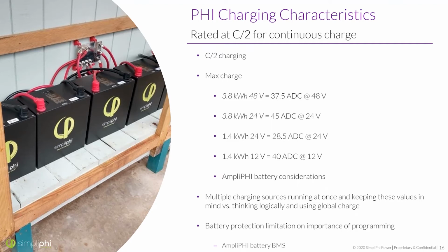I see on a lot of new systems where it can say, hey, you've got a generator and a PV system and the grid. Make sure that the limit is a global limit. So if you set the limit for 37.5, it will make sure that the entire system will never exceed that, no matter what's running. Now, it makes sense logically. Your generator typically isn't going to be running the same time as your PV, but it's something to keep in mind if you've got an older system, for sure.